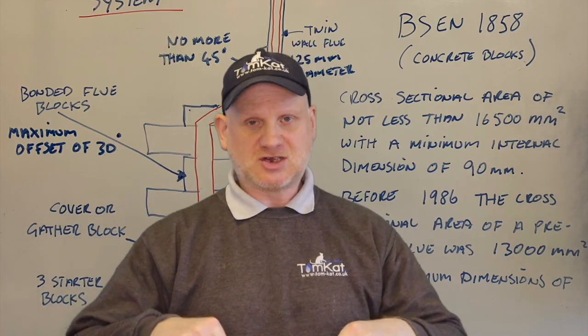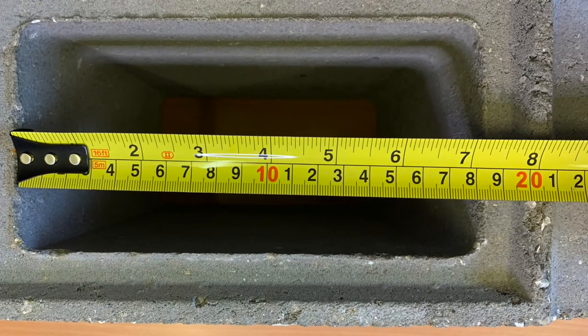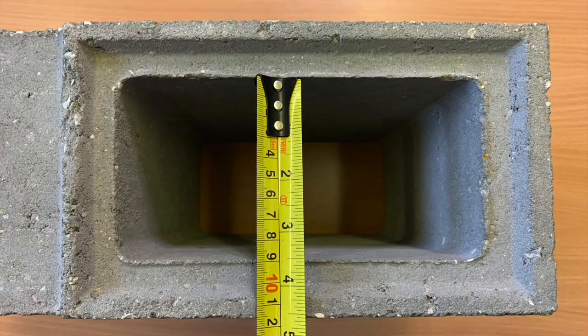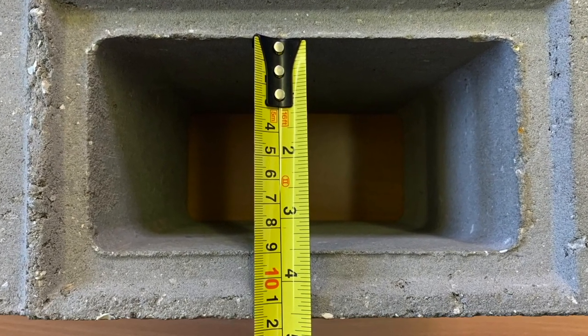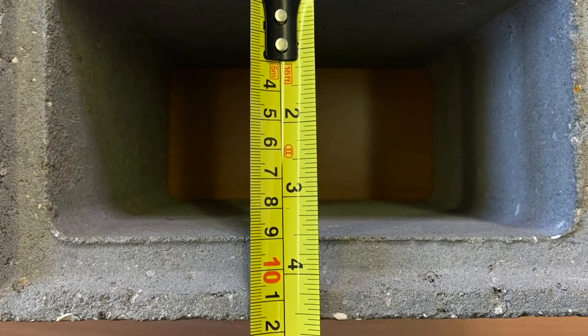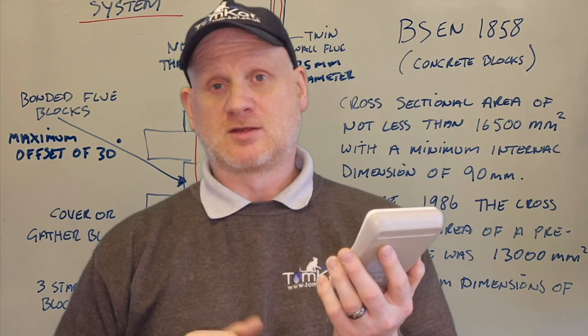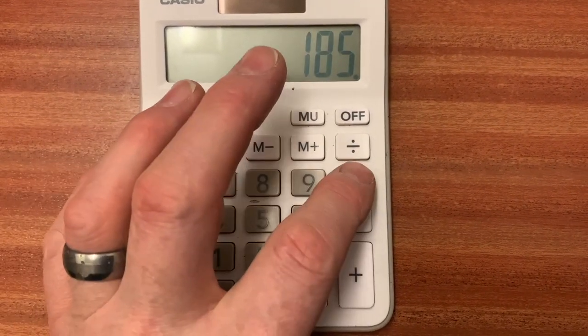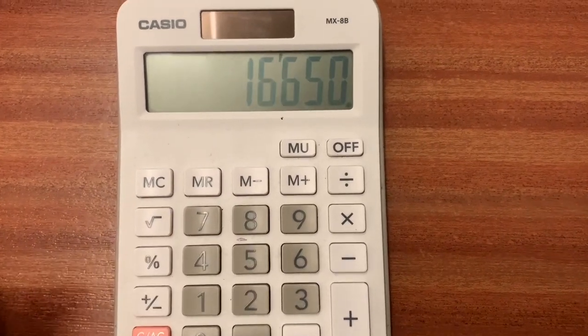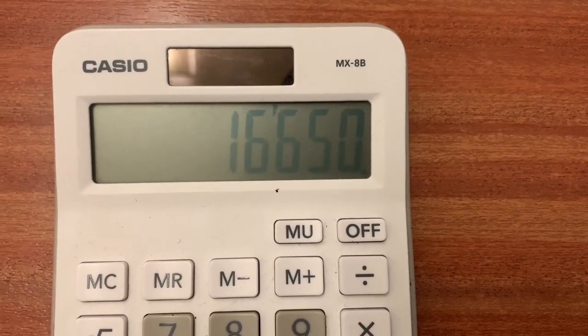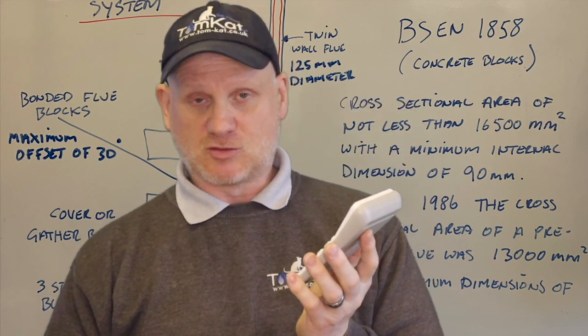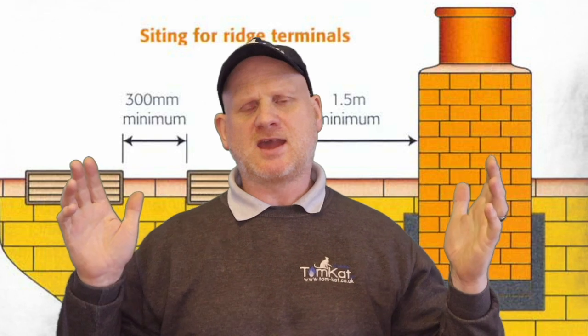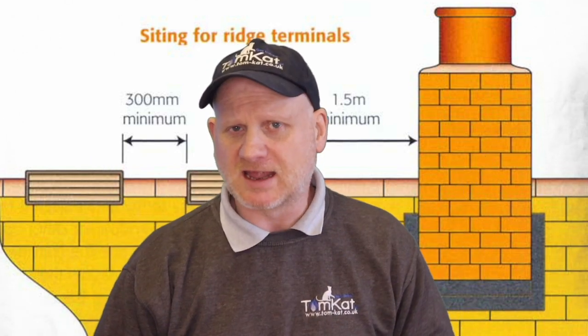Let's measure these blocks. This flue block is 185mm long and has a minimum width of 90mm. So 185 times 90 gives us a cross-sectional area of 16,650mm² — which means it's big enough and meets the current standard.